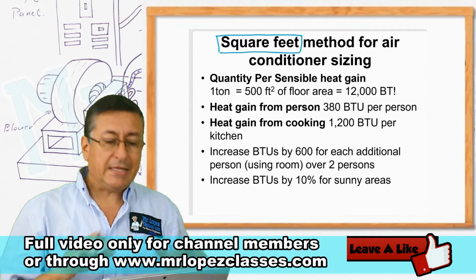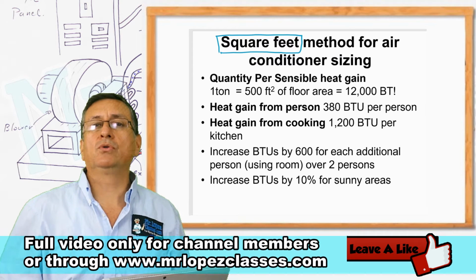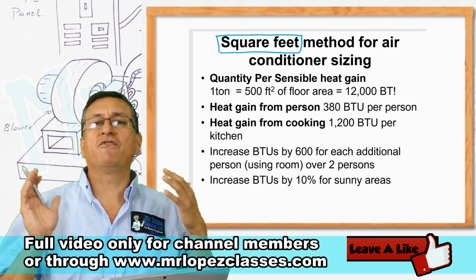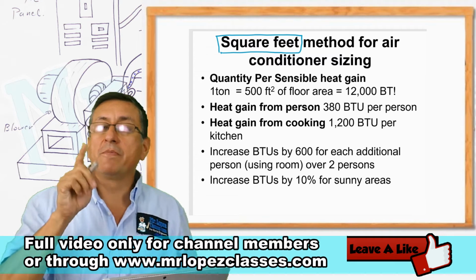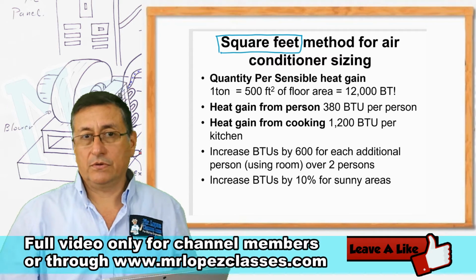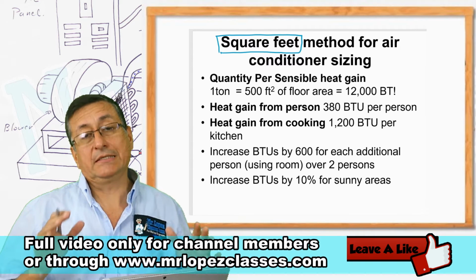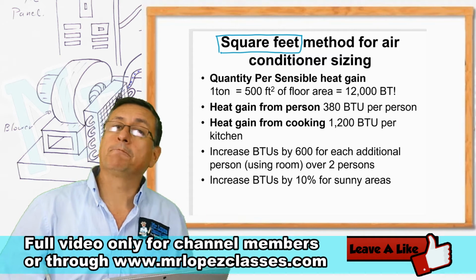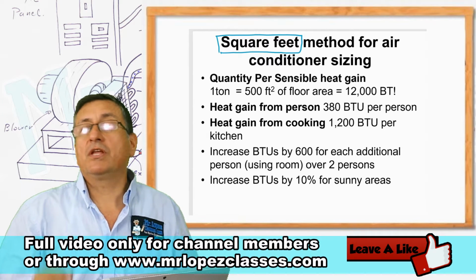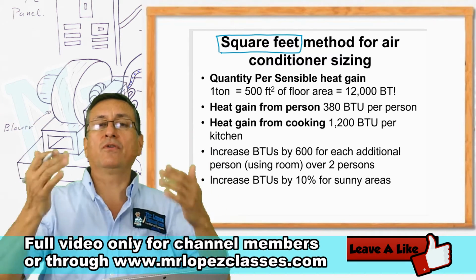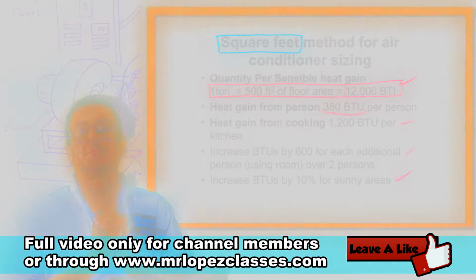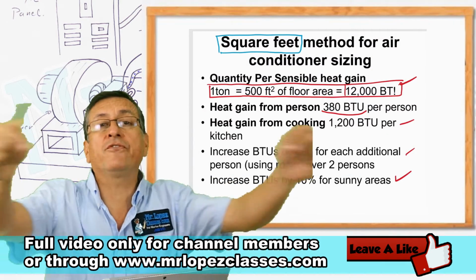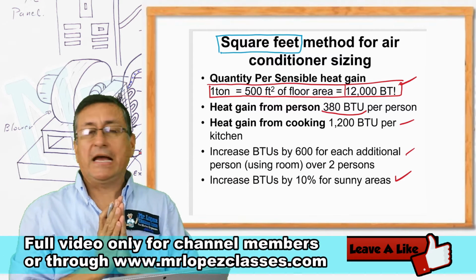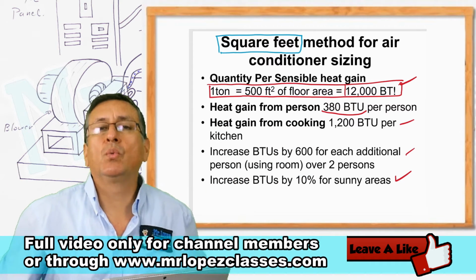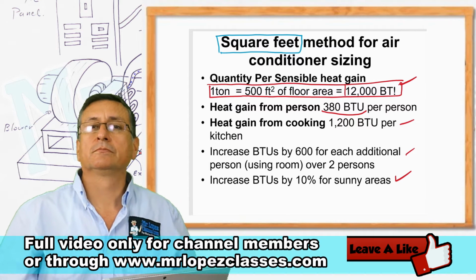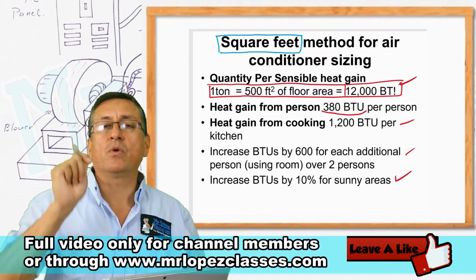Yes, and this method is good for our boats. The structure of our boats is fiberglass. Remember, fiberglass is a good insulator of temperature. This is a great advantage. And another important thing is that the external color of the majority of the boats is white. Per each 500 square feet of area, I need a minimum of 12,000 BTUs, or 1 ton per each 500 square feet.